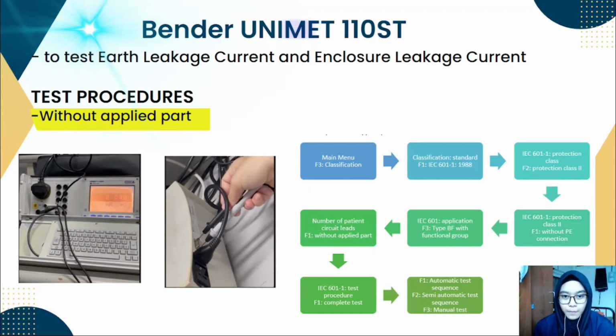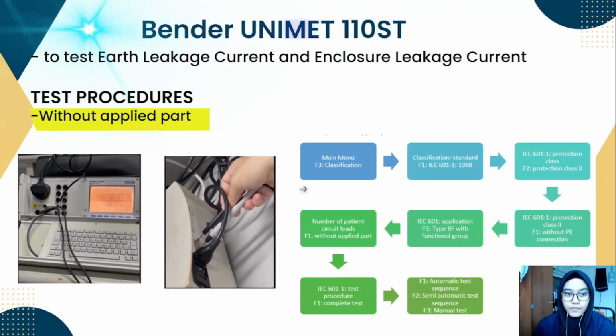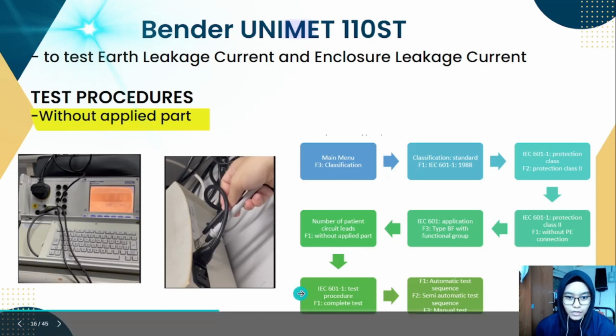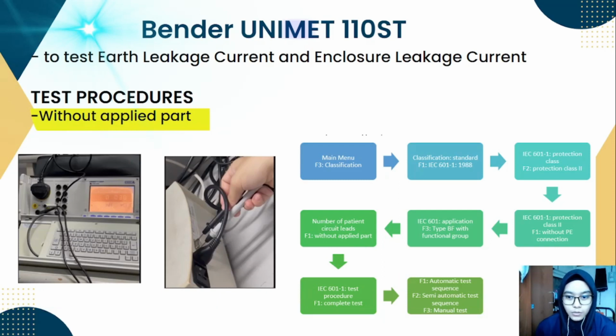We can choose the following options on the monitor of the Bender. First the classification, then the IEC 60601. Because the tonometer is class 2, we choose protection class 2, then without the PE connection, and type BF because the tonometer is a type BF medical device. Then without applied part, because we want to find the earth leakage current and the enclosure leakage current. Then we choose the complete test. Lastly, we can choose either automatic test, semi-automatic test, or manual test. For this one, we choose the automatic test.